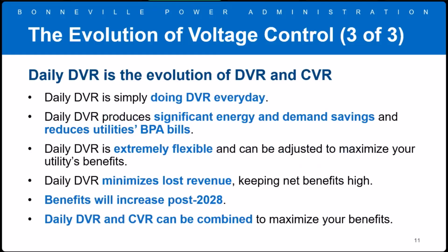So what we're primarily focusing on today is something we call daily DVR. This is an evolution of both the initial demand response measure, DVR, and the conservation measure, CVR. Daily DVR is simply doing DVR every day. It's not a permanent voltage reduction, and it's not installed at all times like CVR. It's a schedule of voltage reductions that happen at times of anticipated high prices or high needs, or when energy savings value provides the most value for the utility—a targeted measure during times of need, but not at all times.